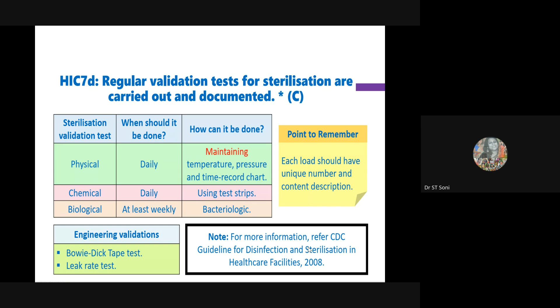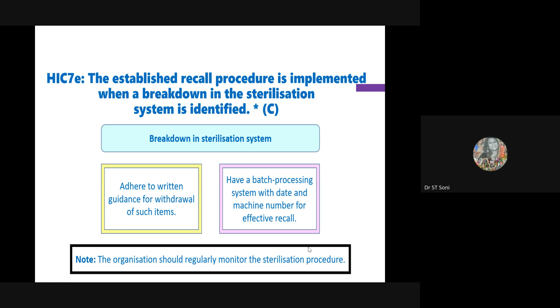So breakdown in the sterilization system, if anything occurs at any time, we need to withdraw the load. So there is something called a recall. Once any of these indicators fails, we cannot issue the load. If it is already issued, we need to recall it back to us and do the root cause analysis and see where the error was, and open it, clean it again, dry, pack, and put it in another sterilizer which is working. Most of the time the failure is because the steam is not generated properly in the autoclave, and because of that there is some leakage inside the autoclave because of the gasket or some coil issues and all, and these can be taken care of.